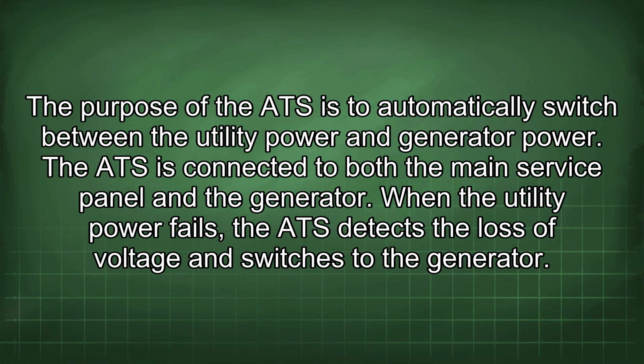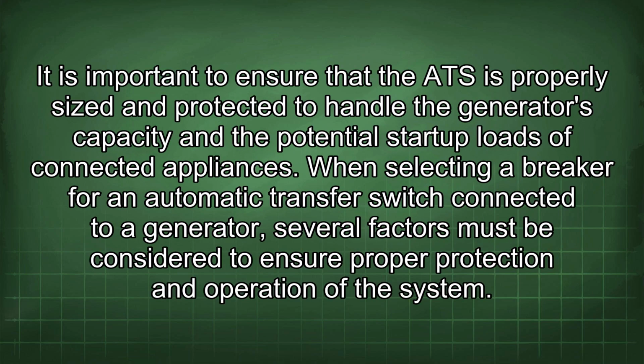The ATS is connected to both the main service panel and the generator. When the utility power fails, the ATS detects the loss of voltage and switches to the generator. It is important to ensure that the ATS is properly sized and protected to handle the generator's capacity and the potential startup loads of connected appliances.